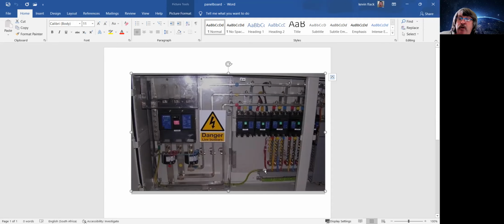When you multi-feed these out to small loads like this, these little cables are not protected by this breaker upstream, and only on extreme current will this breaker in fact trip, possibly protecting them in a way, but it will probably be fatal by the time this breaker trips. These cables will be melted and damaged. So this becomes a very important thing to look at, this interface zone. And it's not just a matter of putting power on and getting power out and thinking, well, everything is hunky-dory in between. It's very important to look at the panel as an extension of the breaker's protection area as well. It's not just the loading of these cables.